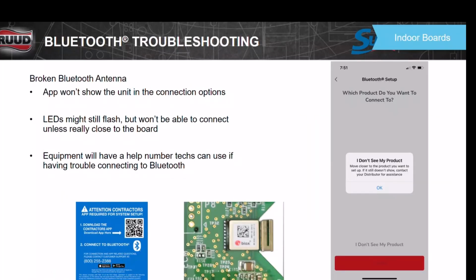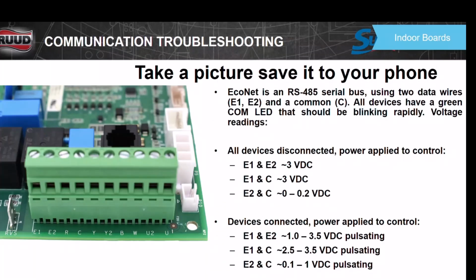The Bluetooth antenna, of course, is, like I said, kind of delicate. They tuck in there on the board, but while you're installing it, make sure it doesn't get hit on any metal or wires where it's going to pull it off. This is another one of those screens that's important for servicing the unit, so take a picture of this. This is the other Kodak moment. This is going to help you determine if you have a communication problem with any piece of equipment, whether the outdoor unit, the air handler, or the thermostat.